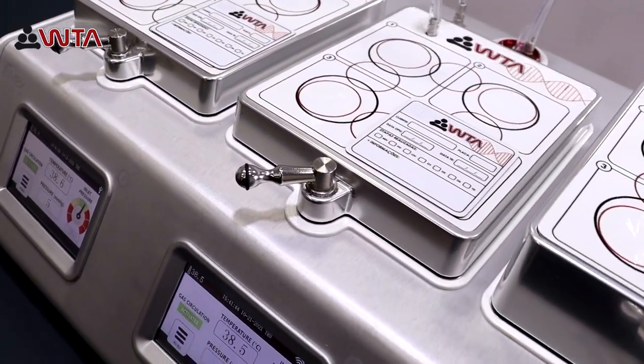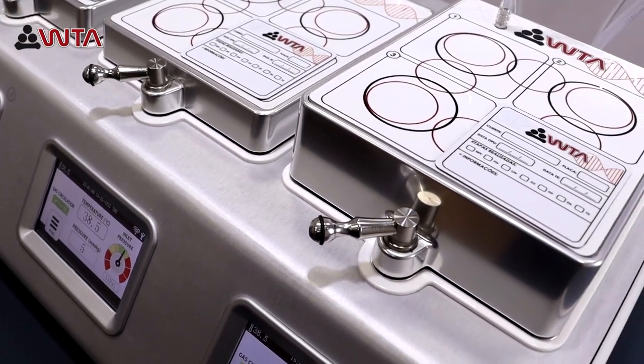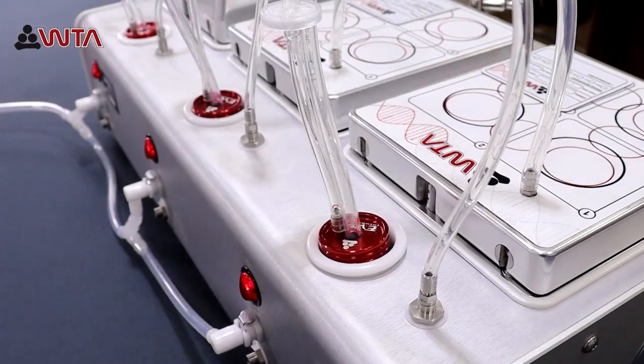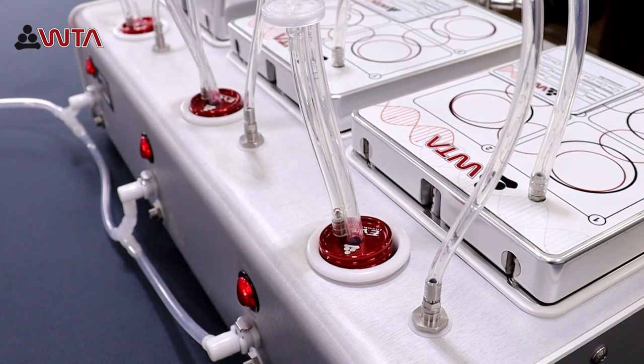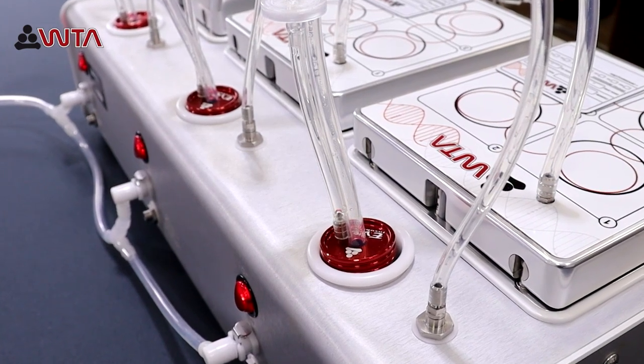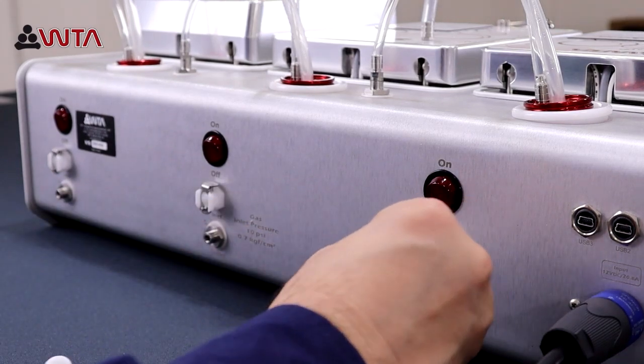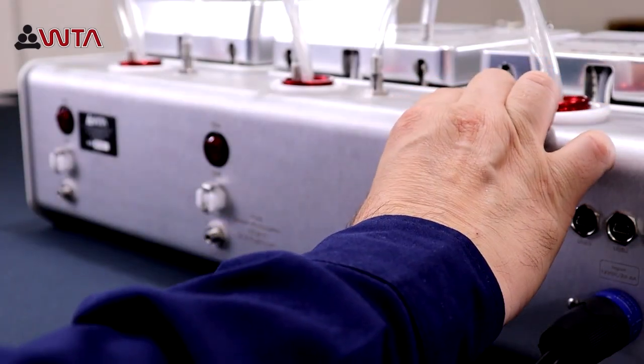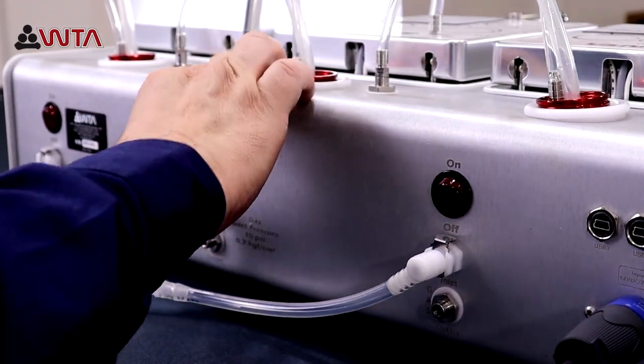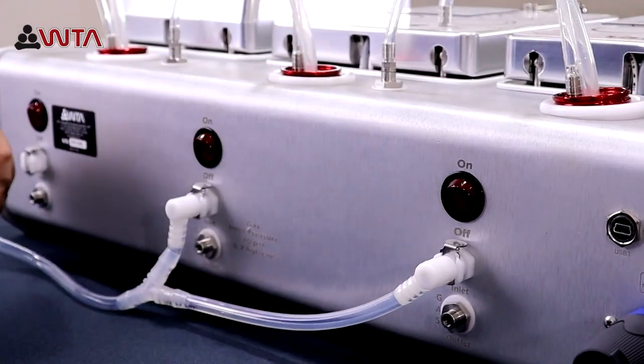Even if the incubator is not used every day, this water must be changed weekly or more often at the user's discretion. Once this is done, it is time to connect the gas mixture hoses to the source. The hose connectors must be connected to the gas mixture inlets located on the back of the incubator chambers, and the other end must be connected to the gas cylinder's pressure regulator.